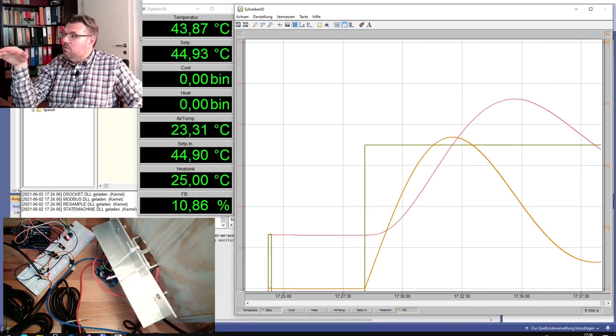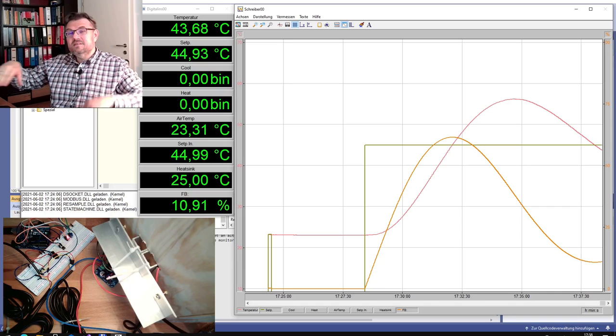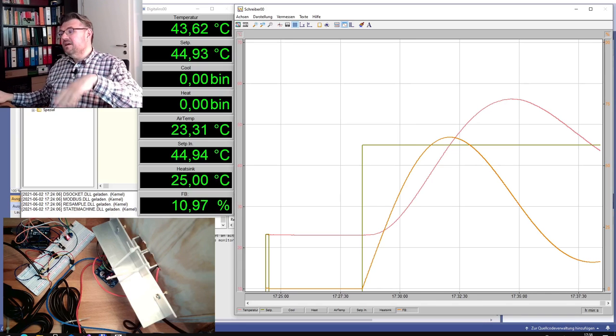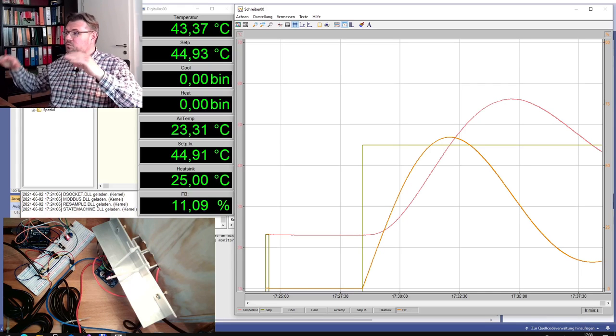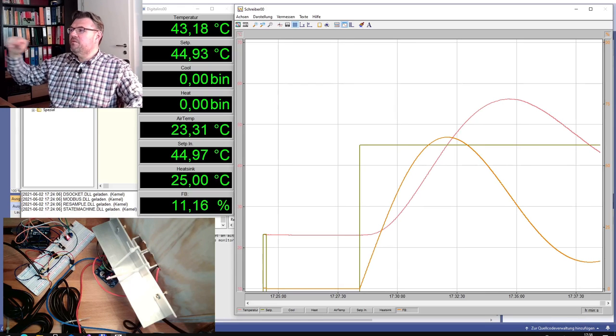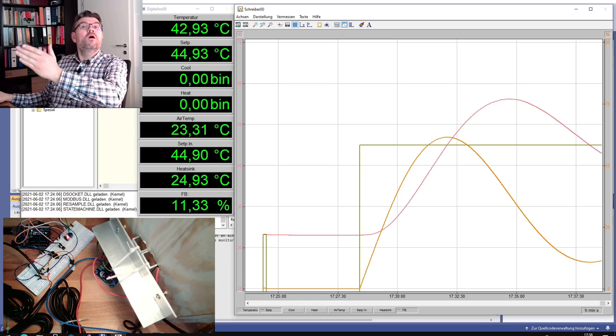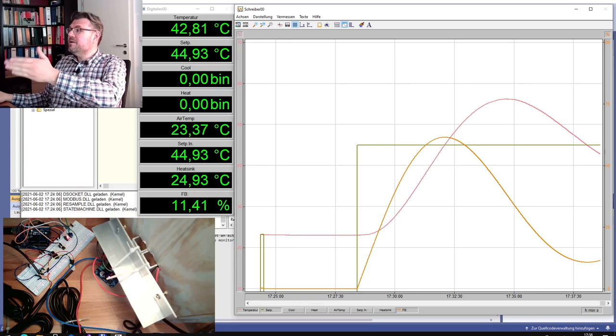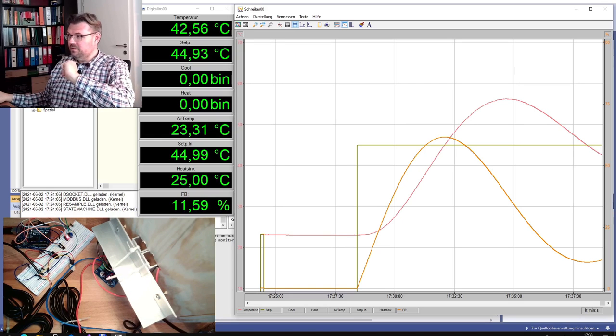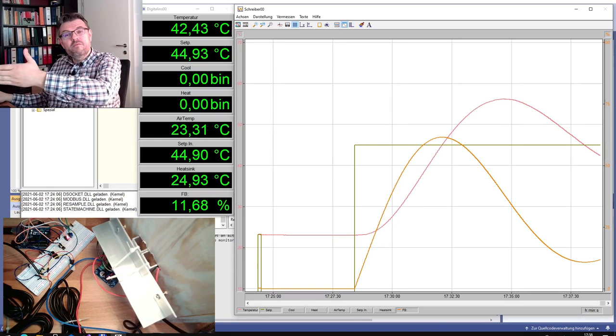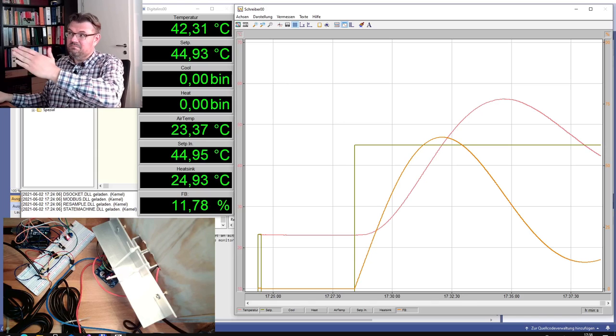See, now we're going below again, and this will start to rise, and hopefully the swinging will get less, and then we'll reach the final value. There's a typical example of what is happening if the TI value is too short, if the integrational part is too aggressive. Even, you see, it's going very slow, but steady.